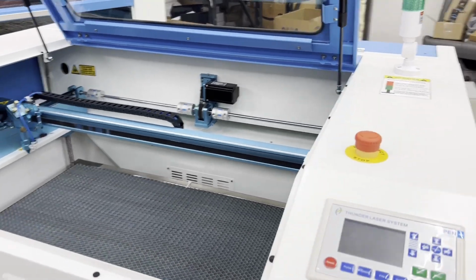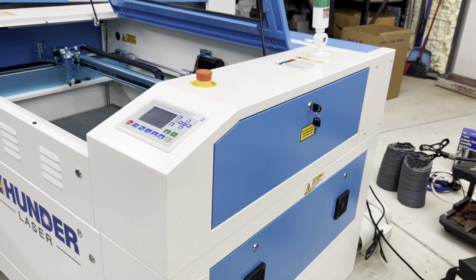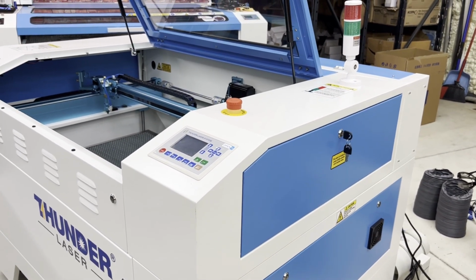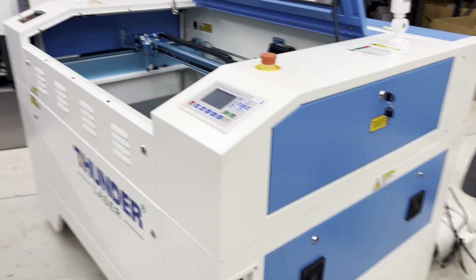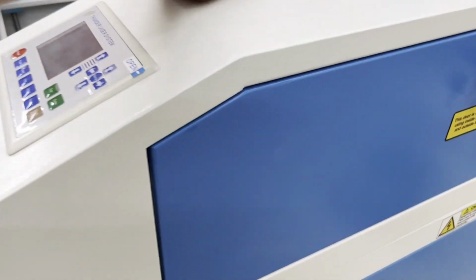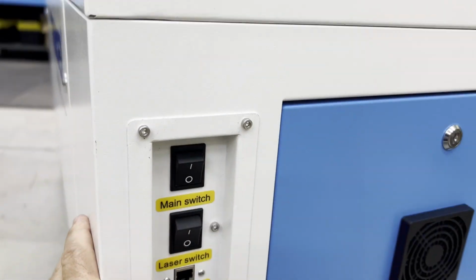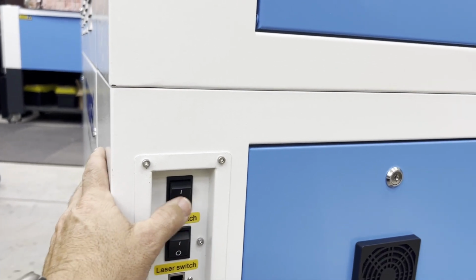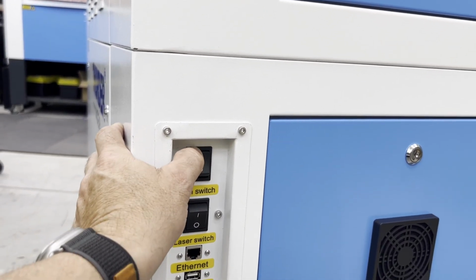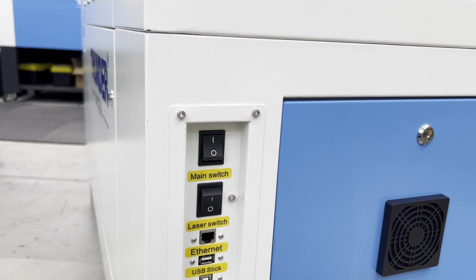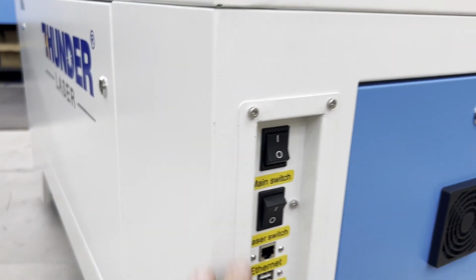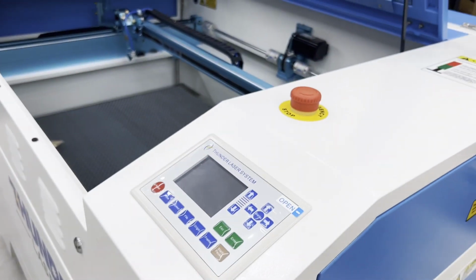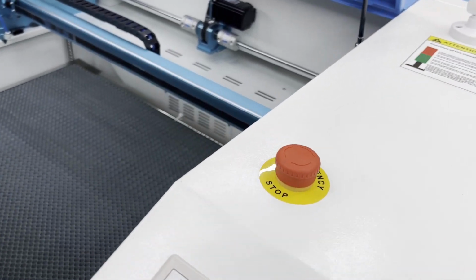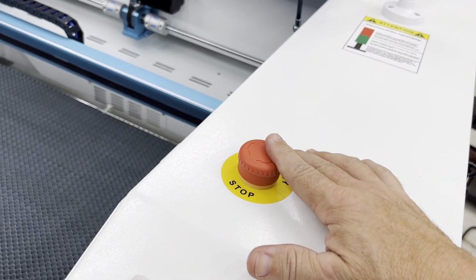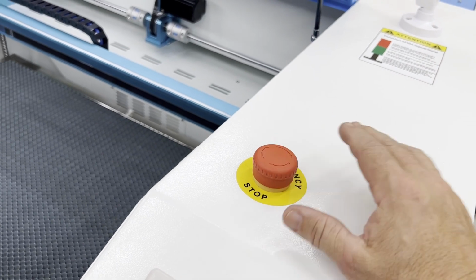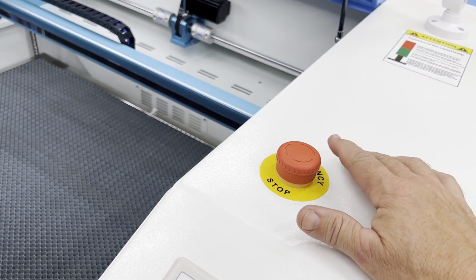Okay, so I did a visual inspection and everything looks to be in order. Now I'm going to turn on the machine and make sure everything is working properly. Again, I want to turn on my main switch first. If you have no response from this main switch — nothing turns on — we need to check our emergency stop, because moving this around, it can get bumped easily.